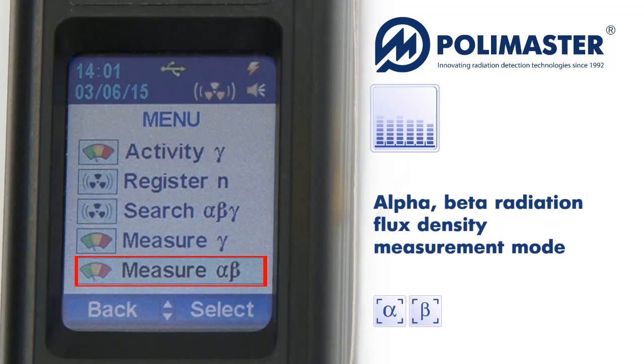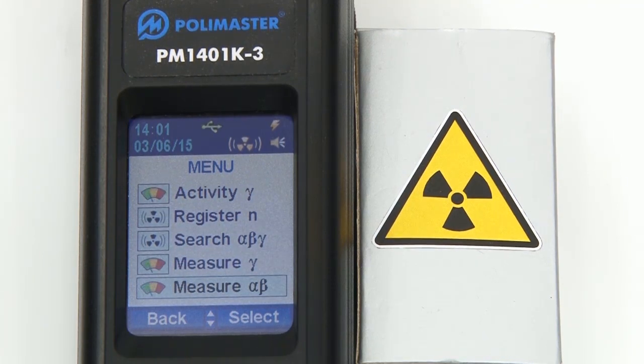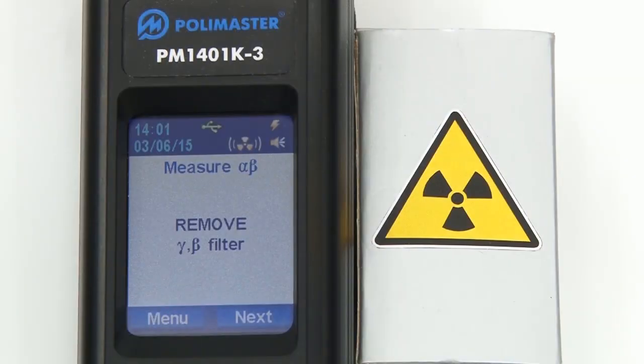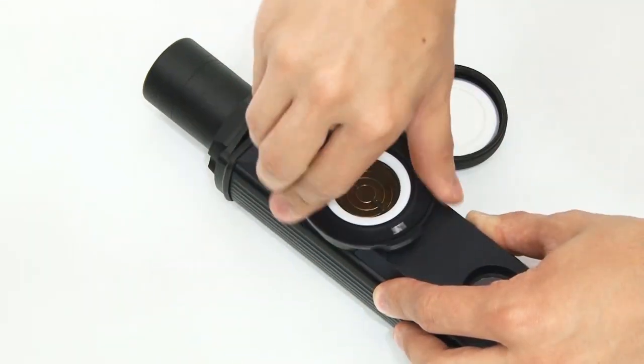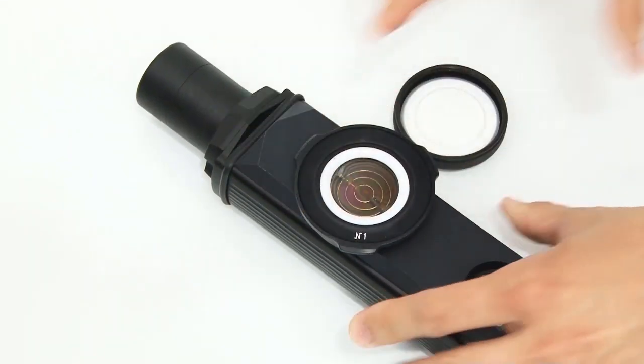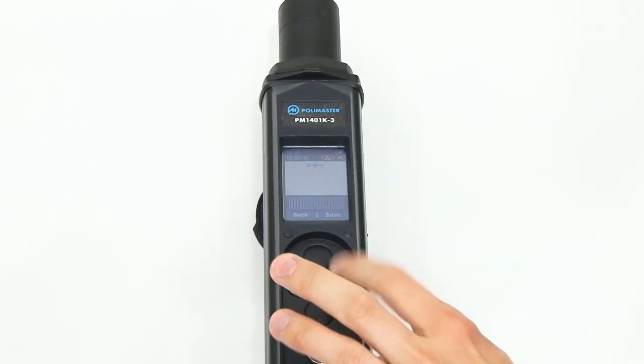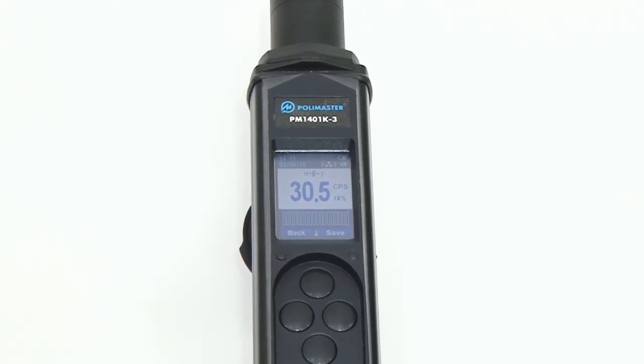PM1401K3 enables measurement of alpha and beta particle flux density. For alpha radiation flux density measurement, select alpha-beta radiation flux density measurement and go to the measure alpha-beta submenu. Then follow the instructions on the screen of the instrument. Remove the gamma-beta radiation filter, install spacing ring number 1, and place the instrument against the contaminated surface. The ring ensures that the distance between the detector and the tested surface is no more than 5 mm.